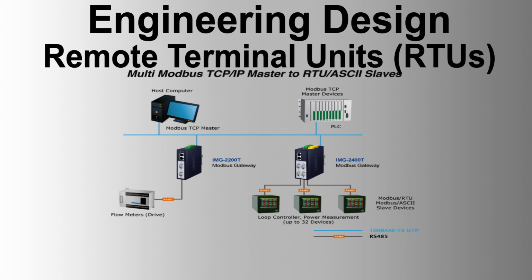2, execution: once the control system receives both select and feedback signals, the operator can give an execute command. This sends a message to the RTU to execute the selected output, resetting the select, feedback, and execute signals. 3, cancellation: alternatively, the operator can reset the select signal to cancel the operation, restoring all other signals to their original state.